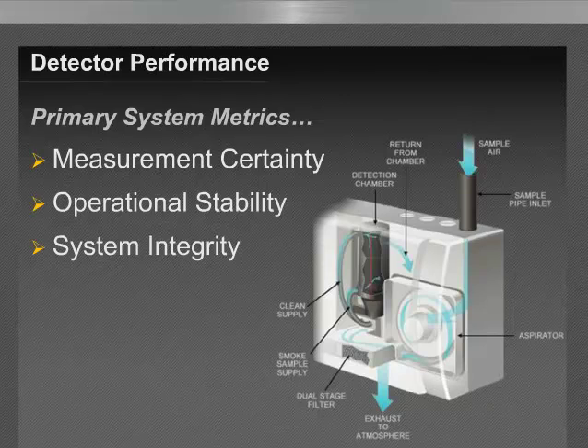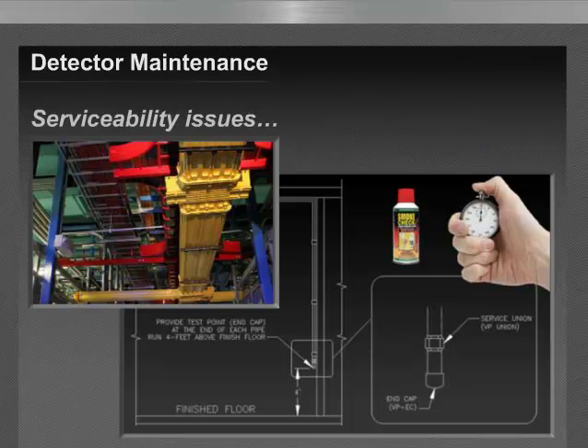And so to bring in the point about detector maintenance, the ease of maintenance for these types of detector technologies, we talk about ease of access and the fact that the detectors can reside down on the wall. You bring the very last sample port to a location where you can easily walk up to it to test and inspect. The intent of an air sampling type system per codes and standards is that you do the smoke transport time from the very last port back to the detector, and you satisfy the requirements for test and inspection of these types of systems. So it greatly reduces the overall impact of test and inspection in a highly congested or problematic area in regards to getting to the detectors once installed.